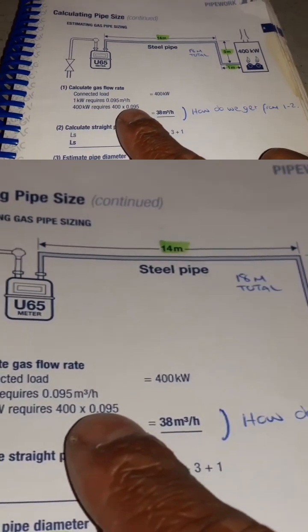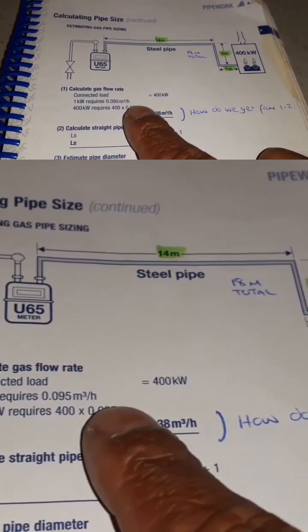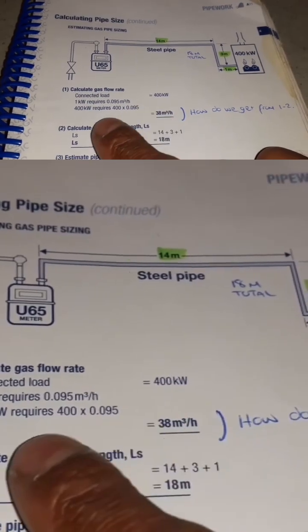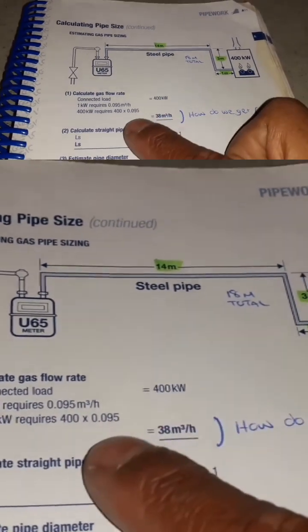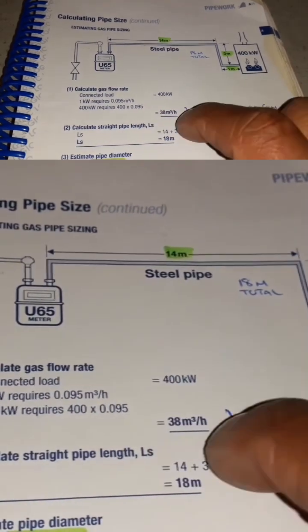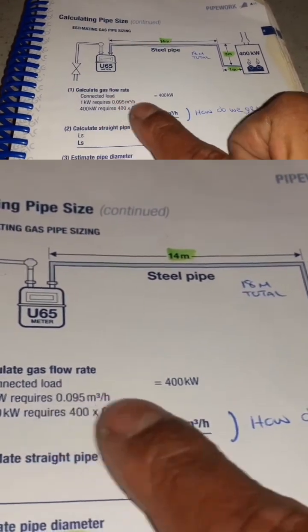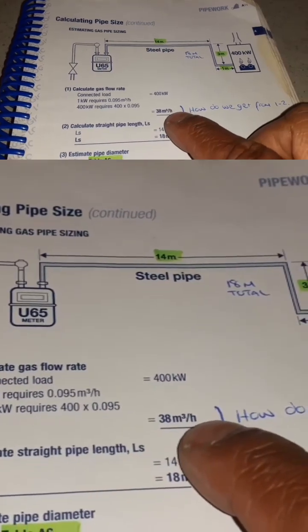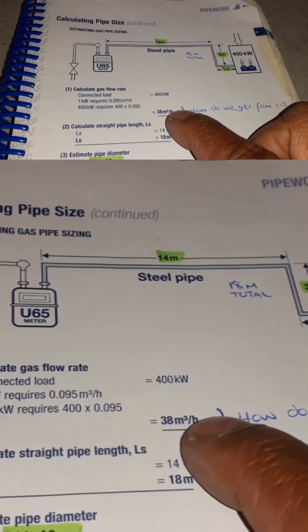So we've got 400 kilowatts that we have here, and we times it by the 0.095 that is required per kilowatt, and we end up with 38 meters cubed of gas an hour.